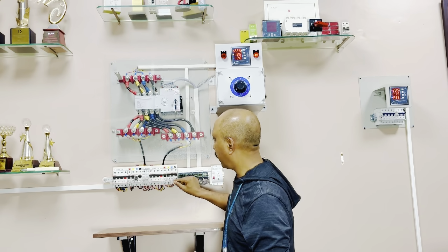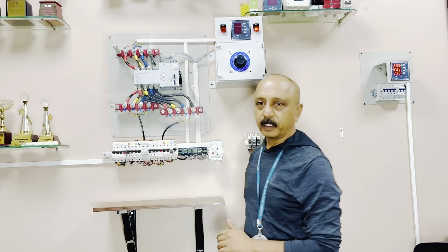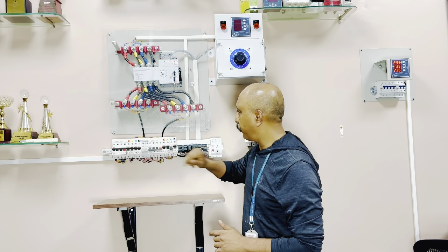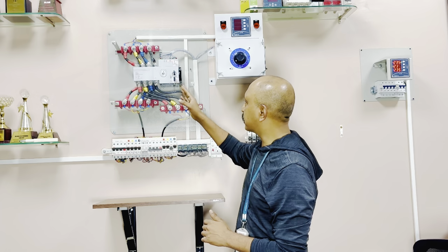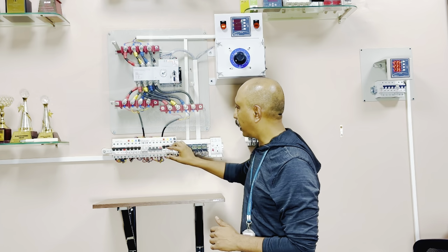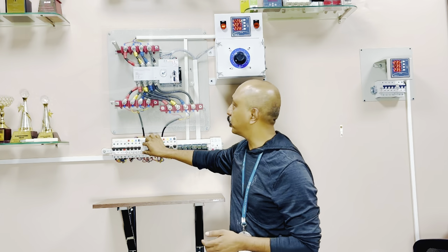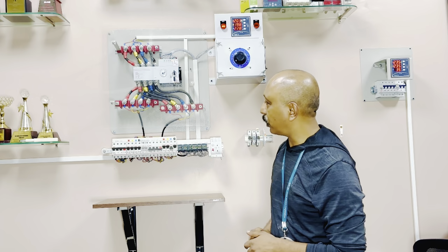Also, I would like to take you to a phase sequence fault. Typically now we have EB fail, the generator is available, so it moves into source 2. Now I am trying to see if the phase sequence fails. I am sure you all understand what a phase sequence fault is. I try to move into a phase sequence fault.